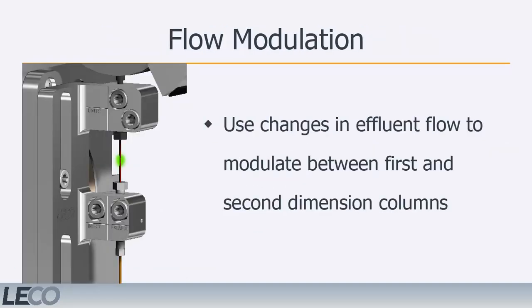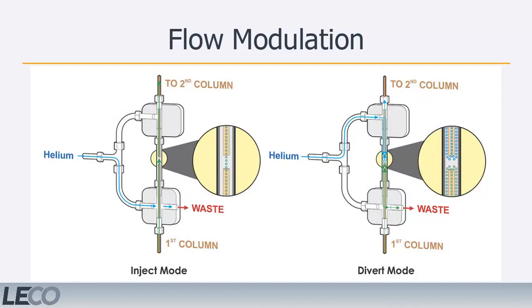An alternative to thermal modulation is flow modulation. A flow modulator is designed to use changes in effluent flow to modulate between the first and second dimension columns. This modulator creates a gap between the primary and secondary columns. When the modulator is switched to inject mode, the effluent is free to travel through the gap unimpeded and transfer into the secondary column. After a user-defined time in inject mode, the modulator is switched to divert mode, during which a carrier gas of higher flow and pressure floods the gap between the columns. This carrier gas diverts the primary column effluent path and prevents it from entering the secondary column. After a set amount of time, the modulator switches back to inject mode and a small amount of effluent is allowed onto the secondary column. This process is repeated throughout the course of the run.